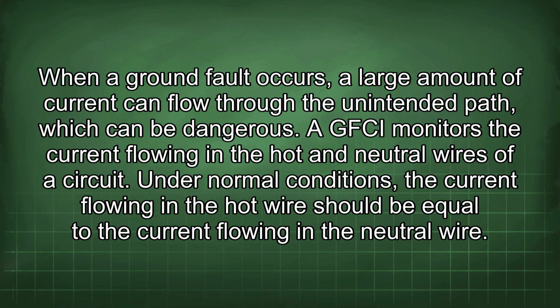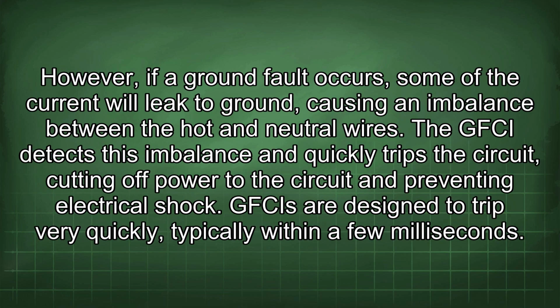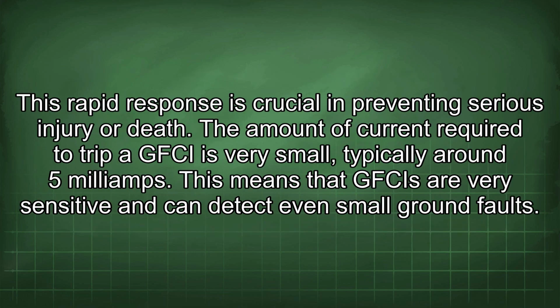A GFCI monitors the current flowing in the hot and neutral wires of a circuit. Under normal conditions, the current flowing in the hot wire should be equal to the current flowing in the neutral wire. However, if a ground fault occurs, some of the current will leak to ground, causing an imbalance between the hot and neutral wires. The GFCI detects this imbalance and quickly trips the circuit, cutting off power to the circuit and preventing electrical shock. GFCIs are designed to trip very quickly, typically within a few milliseconds. This rapid response is crucial in preventing serious injury or death.